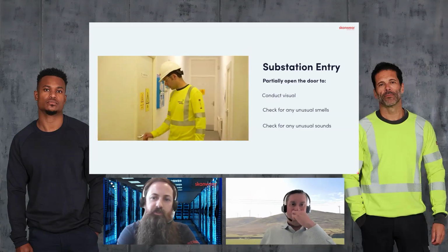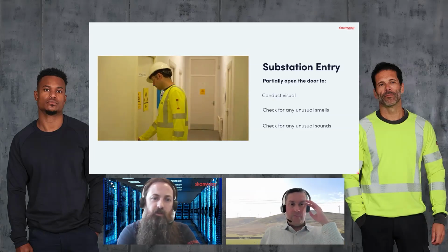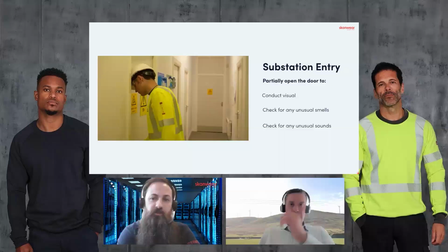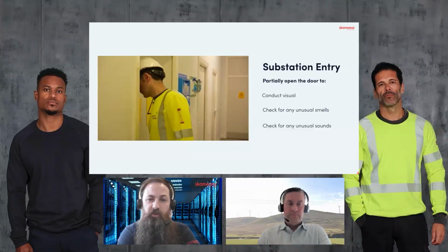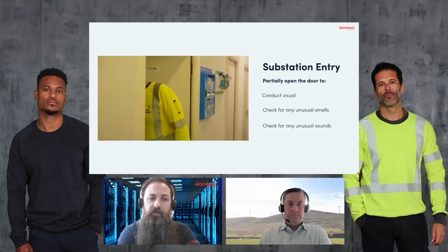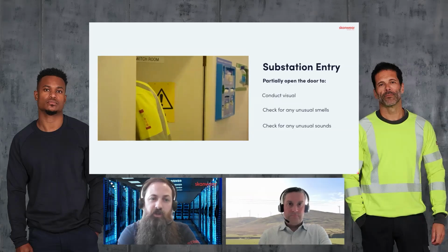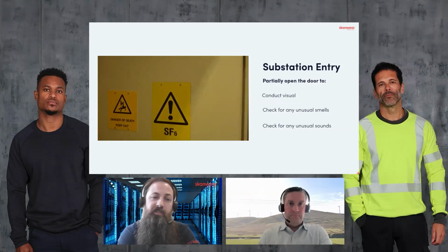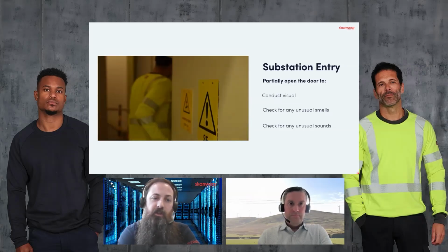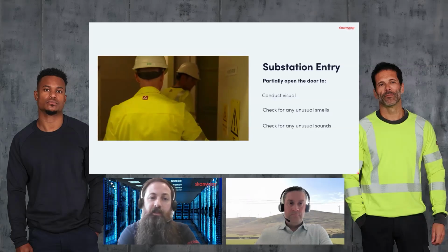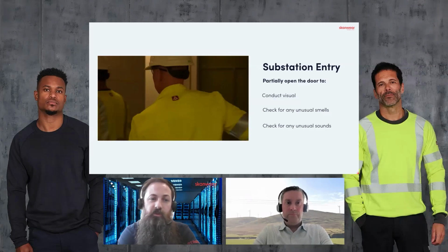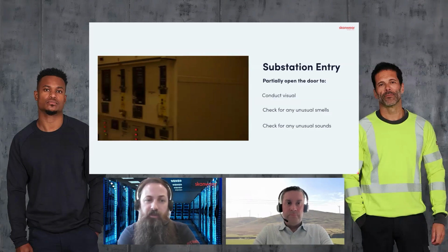They'll partially open the door, use their sensors, conduct a visual check, and check for any unusual smells, like burning, that wouldn't normally be there, and any unusual sounds, like switchgear in distress, maybe hissing, fizzing, or popping. Once that's done, we'd then access the space.